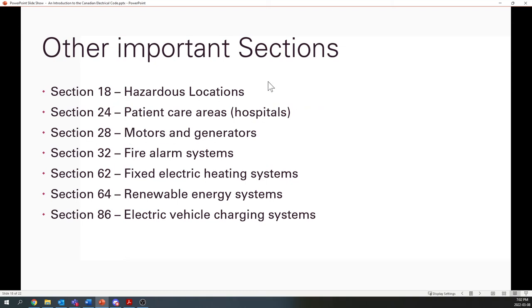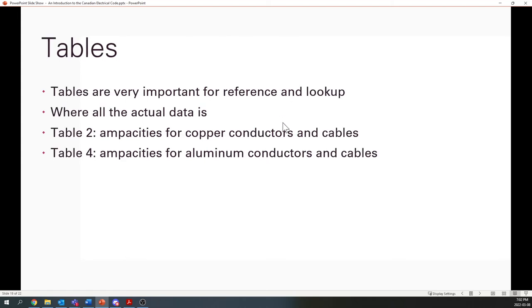And if you're doing hazardous locations design, sections 18, 20, and 22 all have something to say about hazardous locations, corrosive areas, flammable liquid areas, that sort of thing. So in hazardous locations, you need cables, fittings, electrical boxes, receptacles, you name it, lights that are actually rated for explosions. If an explosion was to happen inside the electrical system, in the conduits or something like that, it should not let the explosive gases and the fire spread to other areas, to try to contain the risk.